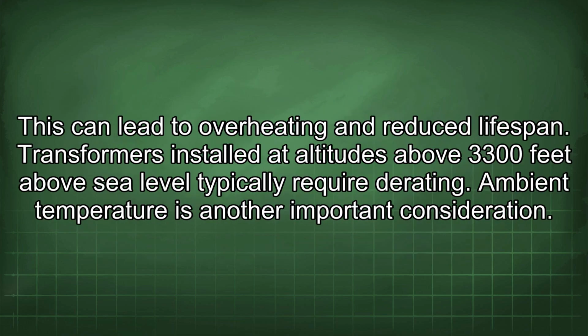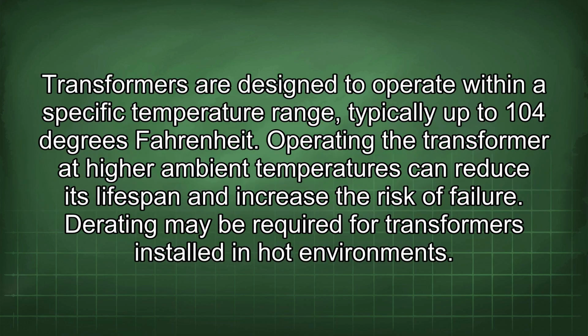This can lead to overheating and reduced lifespan. Transformers installed at altitudes above 3,300 feet above sea level typically require derating. Ambient temperature is another important consideration. Transformers are designed to operate within a specific temperature range, typically up to 104 degrees Fahrenheit. Operating the transformer at higher ambient temperatures can reduce its lifespan and increase the risk of failure. Derating may be required for transformers installed in hot environments.